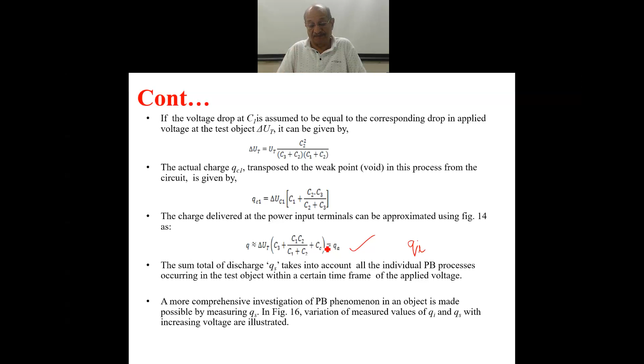The sum total of discharge, QS, S is for sum total, takes into account all the individual partial breakdown processes occurring in the test object within a certain time frame of the applied voltage. A more comprehensive investigation of the partial breakdown phenomenon in an object is made possible by measuring QS, but very few partial breakdown detectors are designed to measure QS. I had one, and most of the measuring instruments are designed to measure QI, that is the partial breakdown discharge at the single location of highest intensity, QI.